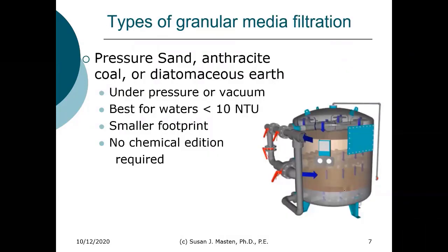So with pressure filtration, typically, these are used for smaller systems and high purity water. So you're looking for waters that have less than a few NTUs in the raw water. And you're looking typically at plants less than about 50 MGD, which is actually still a fairly big size plant. Where I've seen these used most is actually in smaller plants.